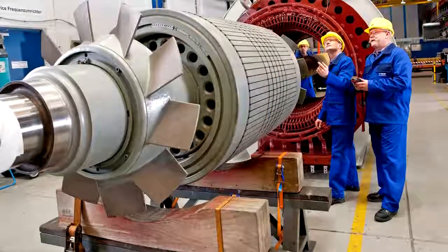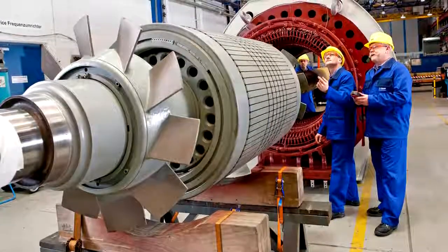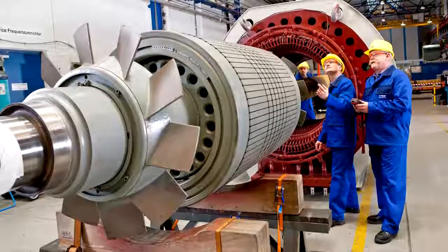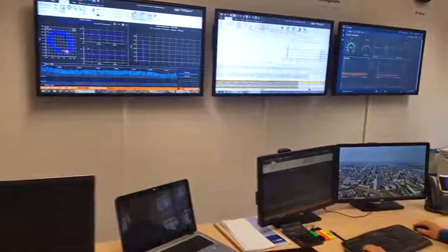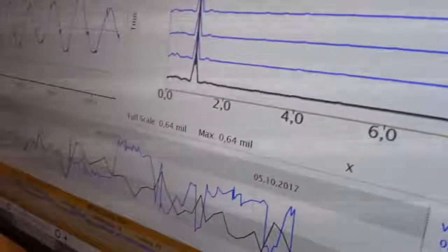BASF Rotating Equipment Department started in 2013 a market research for a new machinery protection and condition monitoring system. SETPOINT and some other manufacturers met most of the BASF requirements. And the most important benefit of the SETPOINT system was to use the infrastructure on the customer side to stream vibration data directly from the protection monitoring system to a PI System.